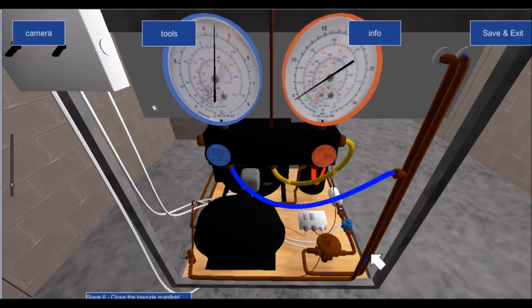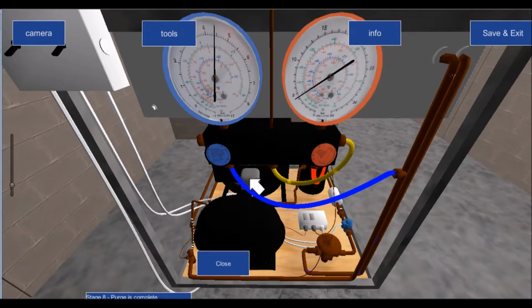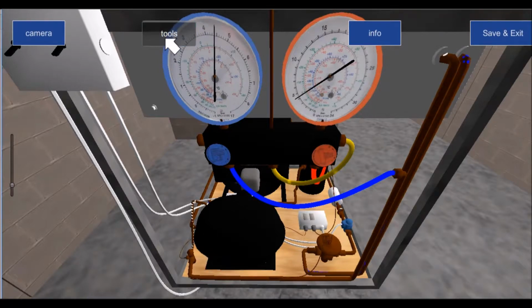Now that we have completed that purge, one of the steps it tells you here is to close the low side manifold. And that's very important that we close that manifold, and I close the high side manifold. The reason why is because when I go and get my valve ratchet, as you can see, there's 5 bar here, there's 4.5 bar here, 4.5 bar realistically. That has stayed the same even though I've closed these two valves.